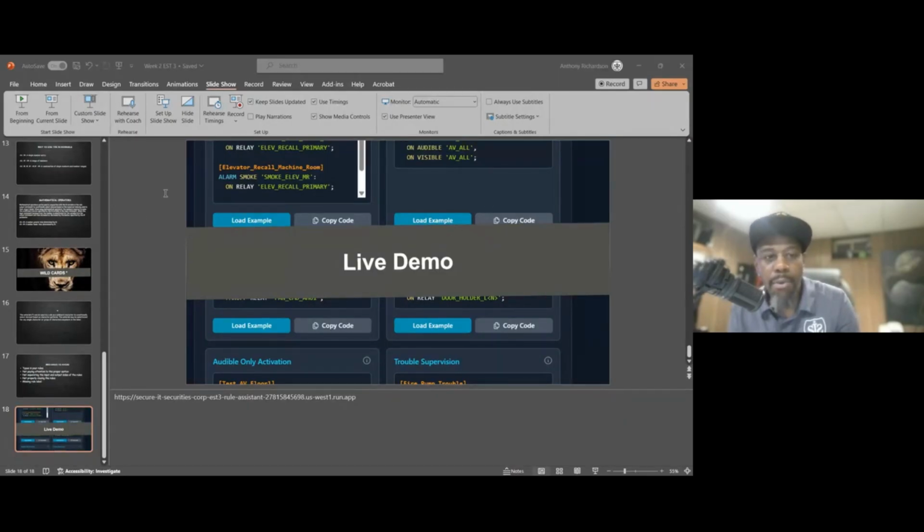So it's alarm level, any level pull station, any number pull station, because each object or each point type or each device needs to have a unique label. So to change the label, just change the number. So we're going to send the account number plus send alarm. Once the point goes active, you will put the account. This is the label for the Modcom, or this particular account inside of the Modcom. So whatever that account number is, 123400001, whatever that account number is, you would use that account number. Then a message, whatever the message is for that particular point type.